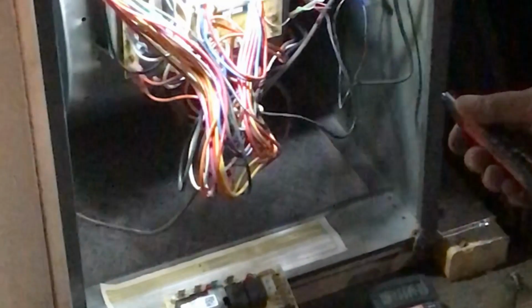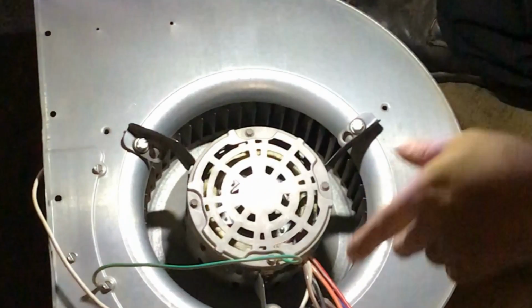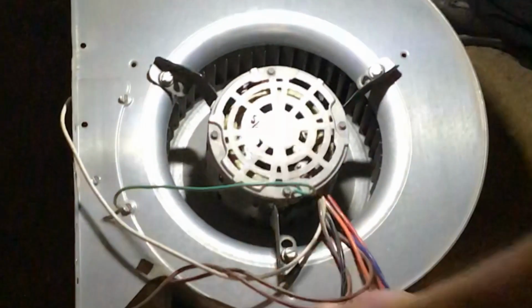These are a lot easier to replace than an outdoor unit. It's a lot less to take apart. Take the board off, transformer out of the way. There's two screws at the top, and the whole cage slides out as a unit. And in a second, we'll show you what it looks like outside of the furnace. Okay, this is what the unit looks like pulled out.